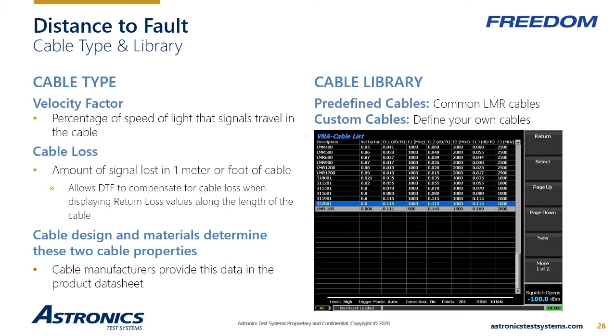The FREEDOM R8200 VNA's distance to fault tool converts the frequency data to time data and equates the time value with distance. To do this accurately, the instrument must be given two important parameters to define the properties of the cable. The velocity factor indicates the speed at which signals travel down the cable. This is defined as a percentage of the speed of light. The smaller the cross-sectional dimensions of the cable, the lower this value will be. This parameter makes it possible to accurately convert time data to distance data with extreme accuracy.